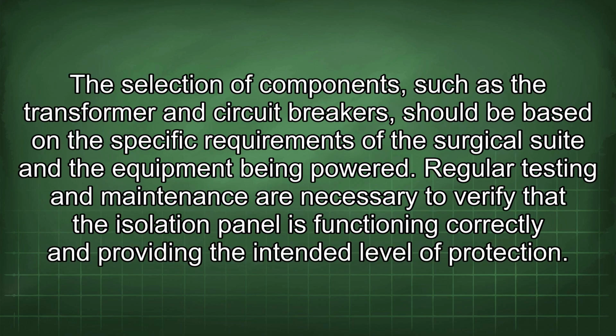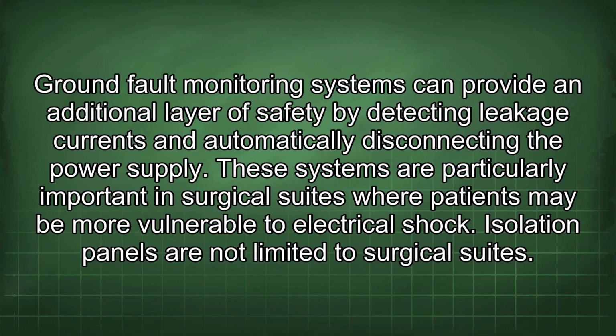The selection of components, such as the transformer and circuit breakers, should be based on the specific requirements of the surgical suite and the equipment being powered. Regular testing and maintenance are necessary to verify that the isolation panel is functioning correctly and providing the intended level of protection. Ground fault monitoring systems can provide an additional layer of safety by detecting leakage currents and automatically disconnecting the power supply. These systems are particularly important in surgical suites where patients may be more vulnerable to electrical shock.